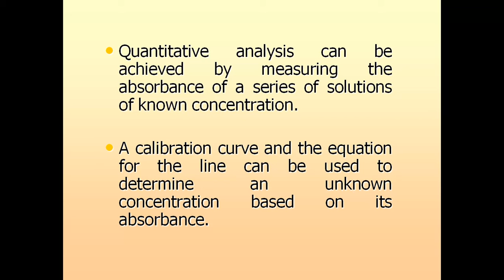And in this analytical technique for AAS, sample preparation is very tedious. We have to prepare the sample. The sample should be properly filtered. There should not be any particulate matter inside, otherwise it will clog the capillary. And the calibration standards, reference material should be taken care of, because your calibration curve should be right.